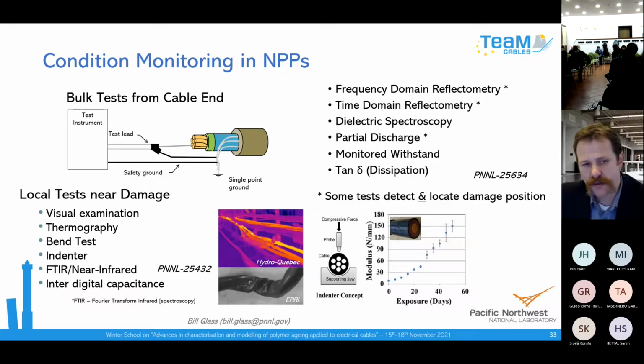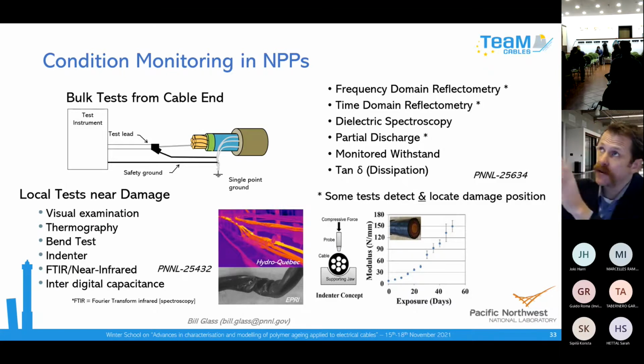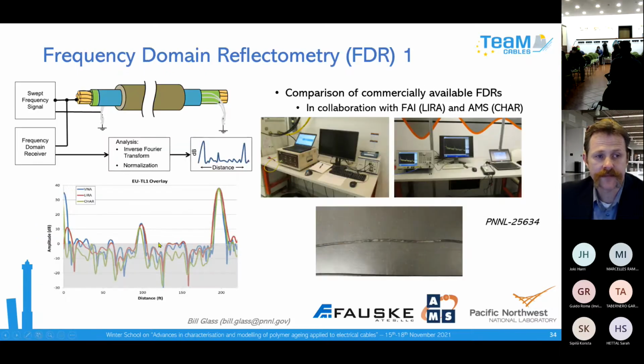Local tests are ones you might do, like measuring indenter modulus, or using the portable FTIR, or seeing a color change in the cable when you touch it during cable walkdowns. These are often quickly measured when you walk through a plant and look for signs of stress. But of course, they're severely limited by what cables are available to look at.